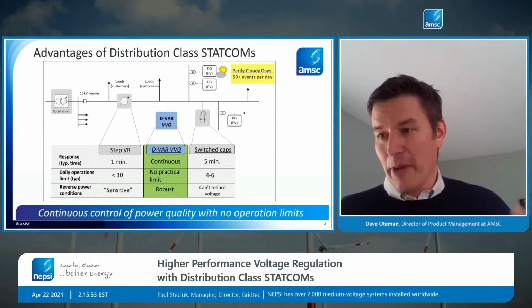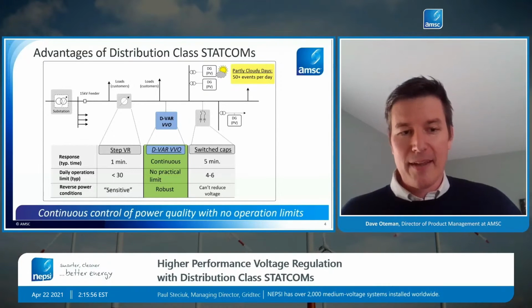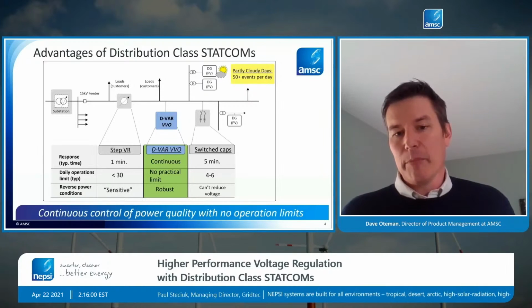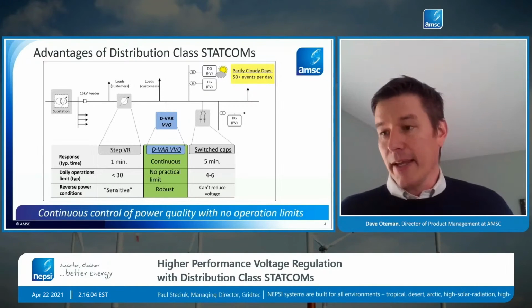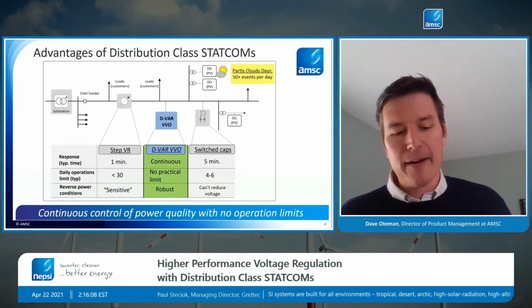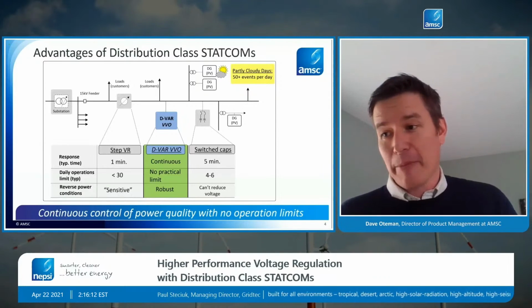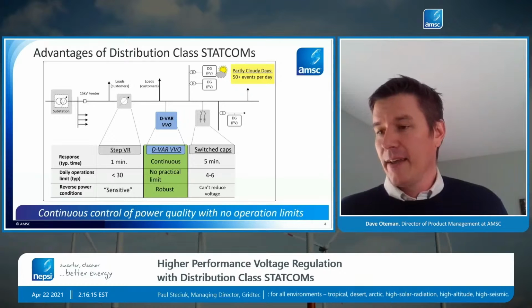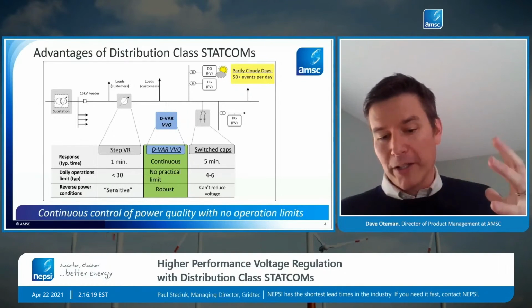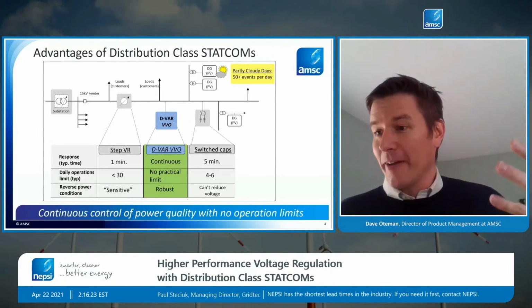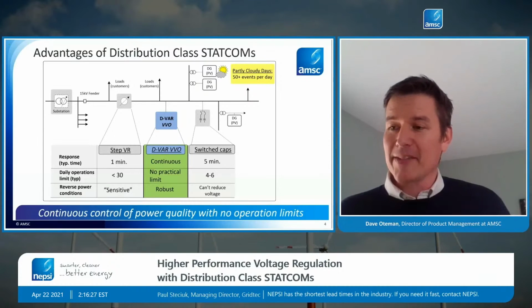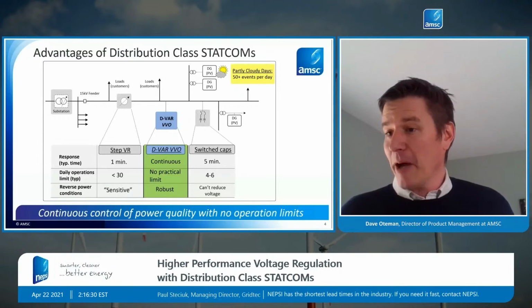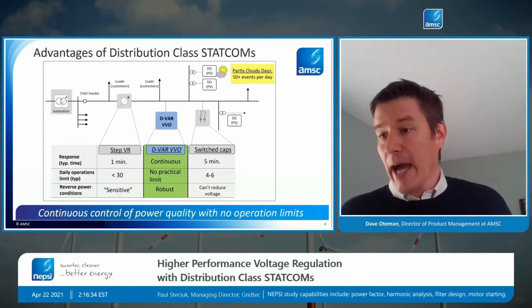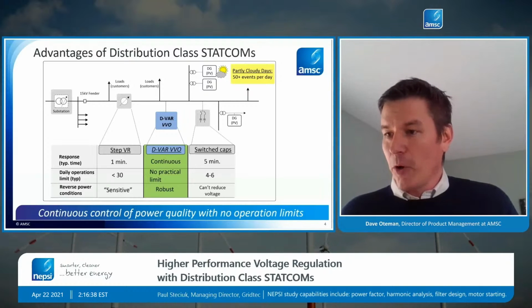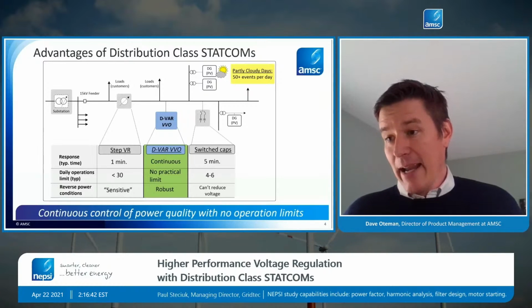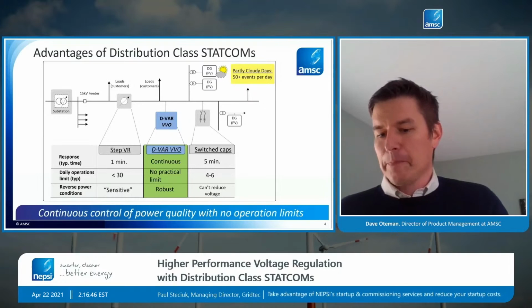They don't have to think about, oh man, is this going to wear out more quickly because now this circuit has variable load on it. And then finally, the ability to handle power flow in either direction is an inherent property of a STATCOM. It just does not care if power is going forward, reverse, or very rapidly going back and forth between forward and reverse. The controls are inherently robust to that, and it's just one control mode. You don't have to make it aware that the power might be changing direction, for example. So those are other nice advantages that our utility customers like about this technology. At the end of the day, we're able to fill that gap where we can control power quality on a continuous basis and not have to be concerned about whether that will wear out the equipment or not.